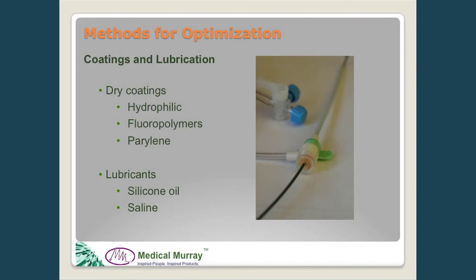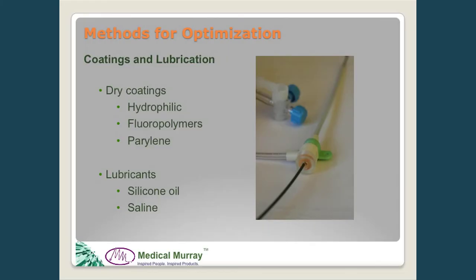Coatings and lubrication can be a real game changer. In applications where high flexibility is needed, we can implement coatings to reduce the loads required and reduce the amount of reinforcement needed to move components. There are a number of different coatings available — hydrophilic coatings, fluoropolymers such as PTFE — and we can also use lubricants like silicone oil to facilitate motion between components.